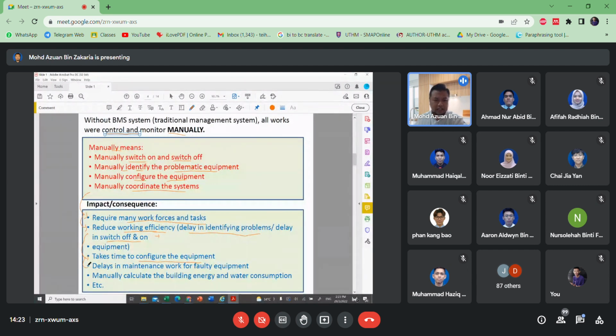And then there are delays in maintenance works for the equipment because without BMS systems, they don't know exactly where the location is, so they need to troubleshoot to check the whole system to find where the problem is. But with a BMS system, each equipment has a sensor, so if the sensor has a fault, they can directly identify and go to the problem equipment.